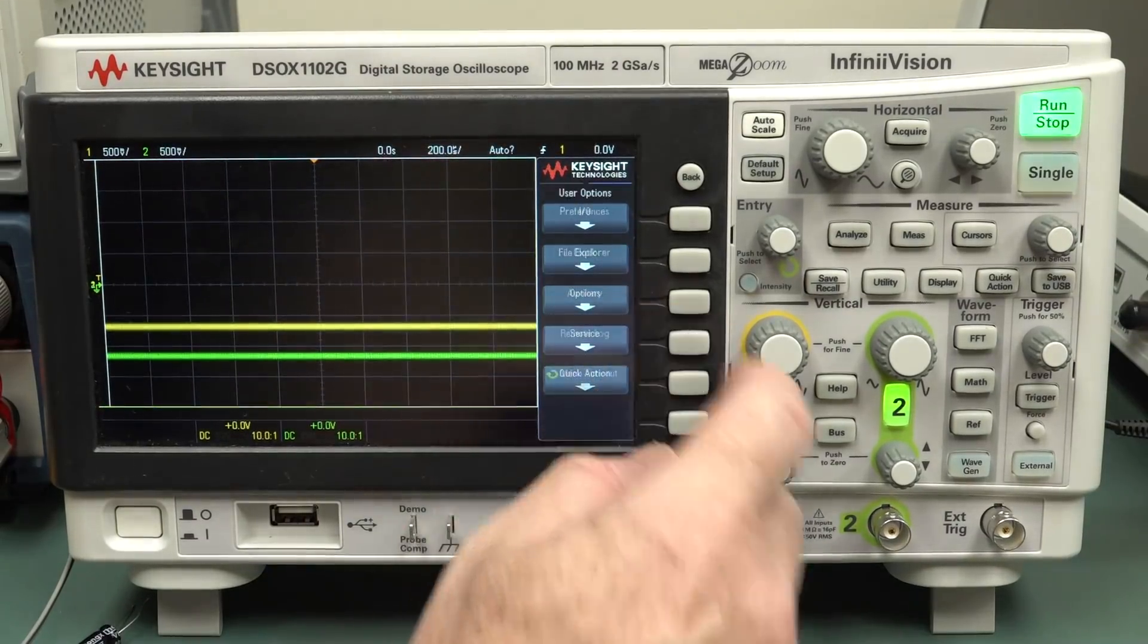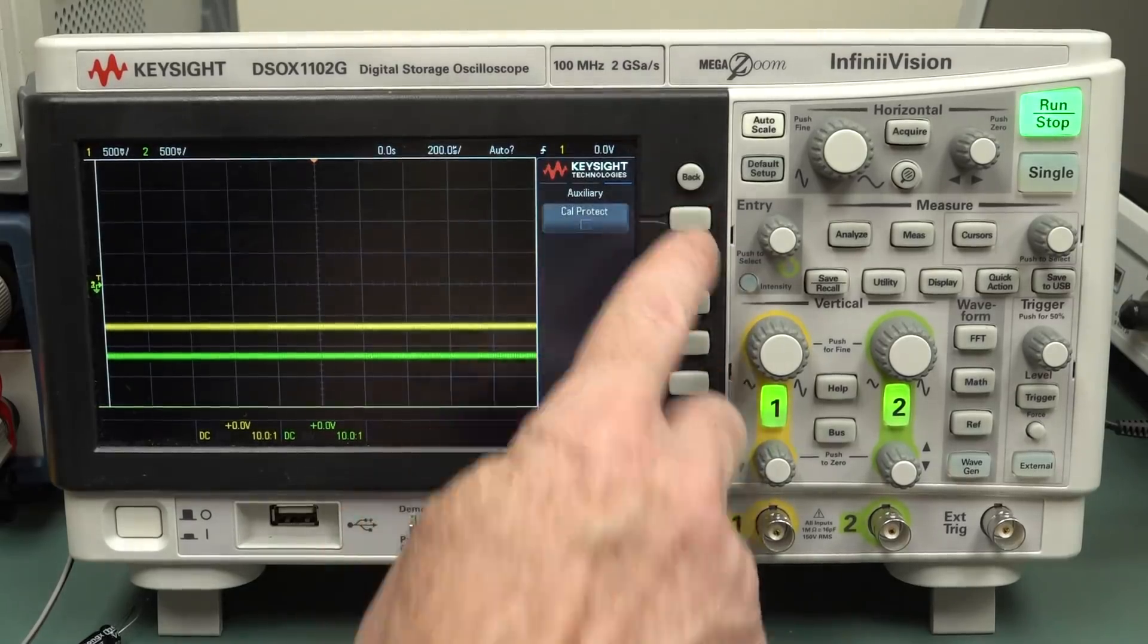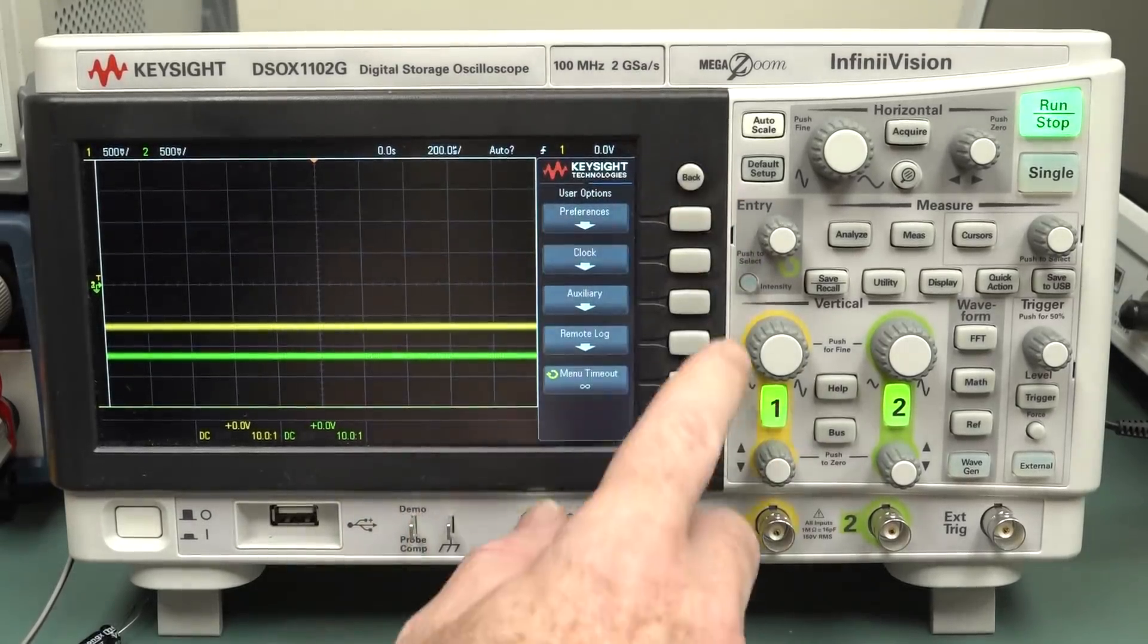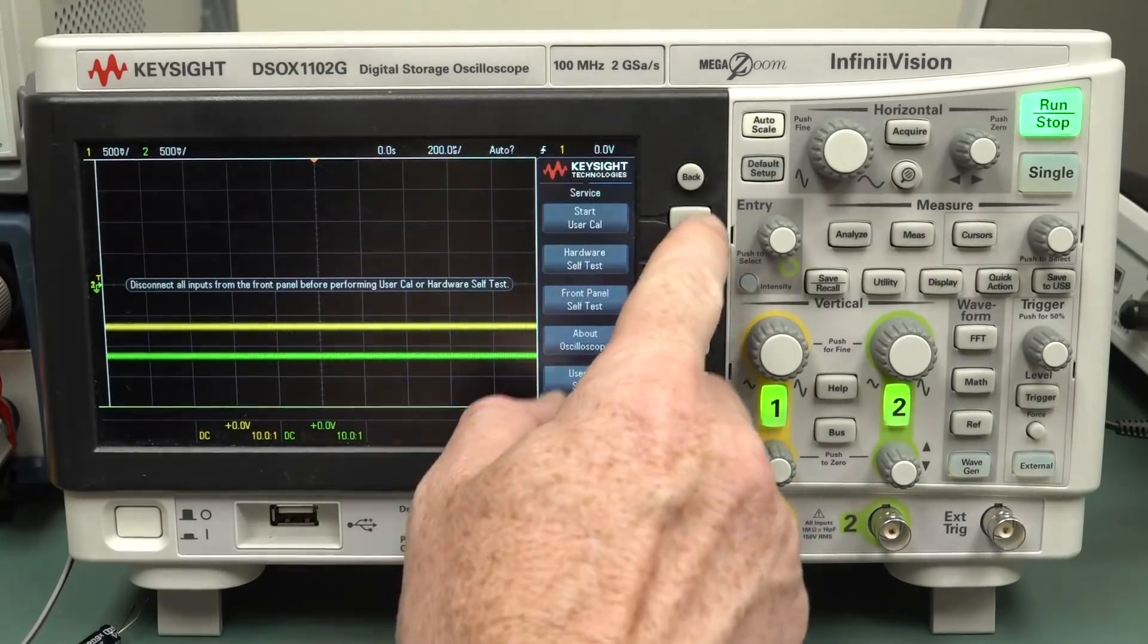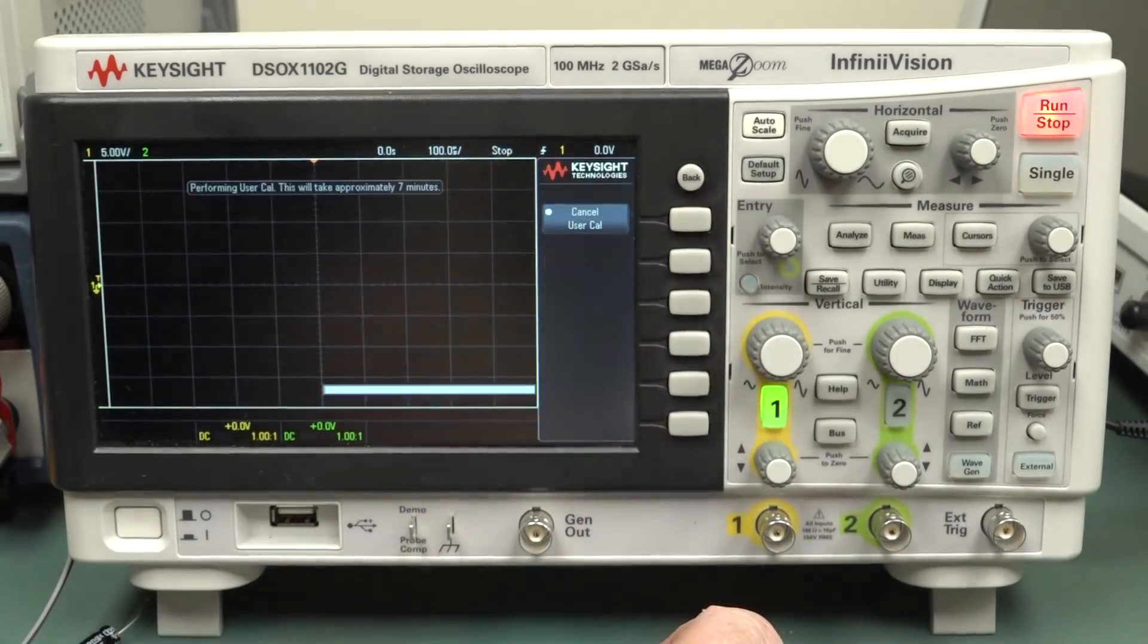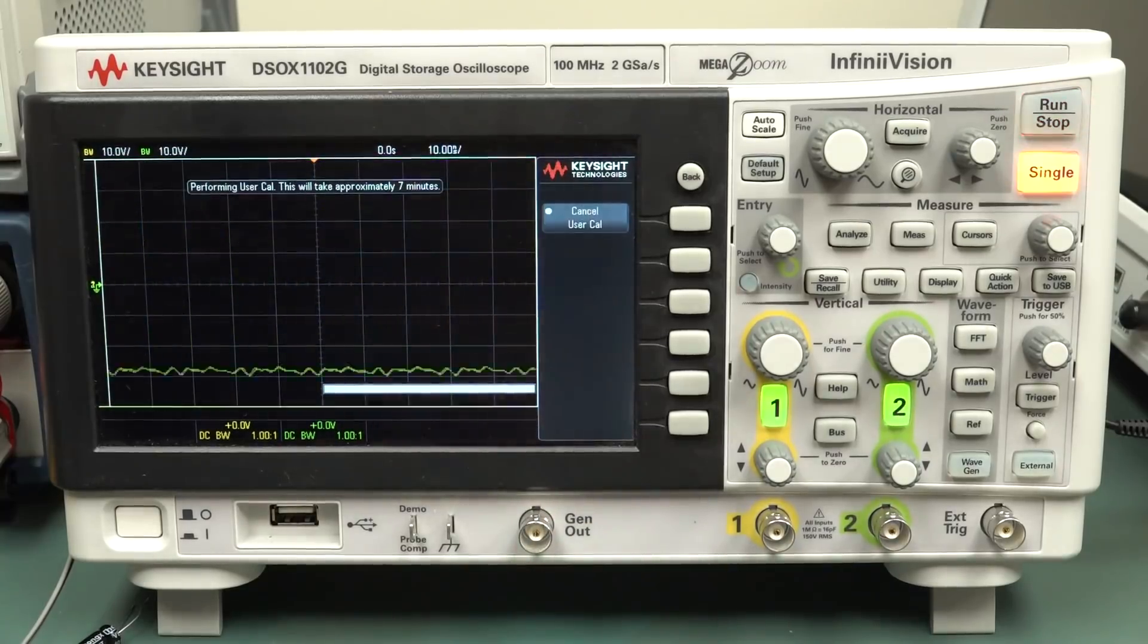Alright, so let's just run that calibration again. You've actually got to go into options here. Auxiliary. And Cal Protect. So you've got to disable the calibration protection. And then you've got to go into service here. And then start user calibration. And boom. There it goes. Take approximately seven minutes.